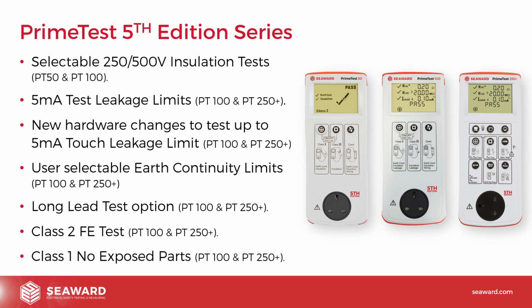And something else we've added in, not really from a 5th edition point of view, but because it's something we're asked about more and more and more, is Class 1 with no exposed conductive parts. So a lot of times you'll come across equipment like office fans, for example, where they have no exposed earth parts. It's all plastic on the outside. It's Class 1. There's an earth connected to the inside, but all the stuff on the outside is insulated. There's nothing there for you to actually test to. So you've got two options really: either physically take it all apart, or you poke screwdrivers in, or all those sort of things, which is generally seen as bad practice.